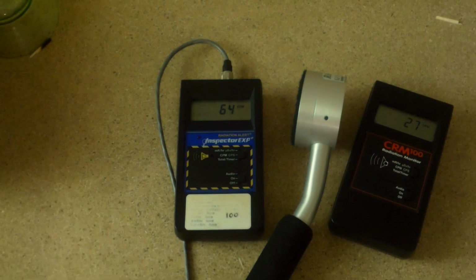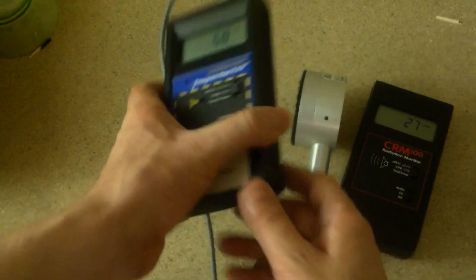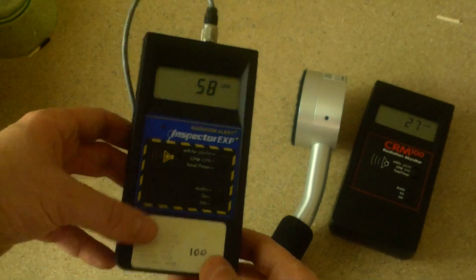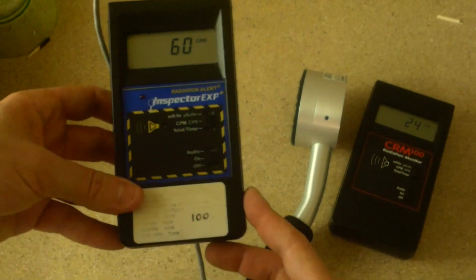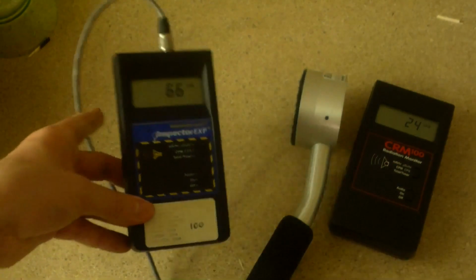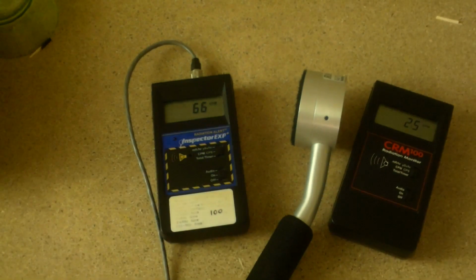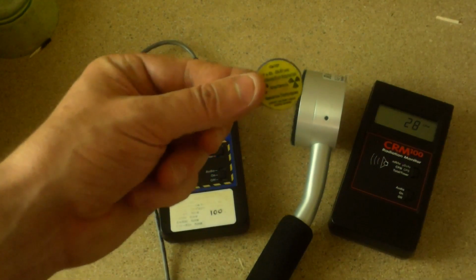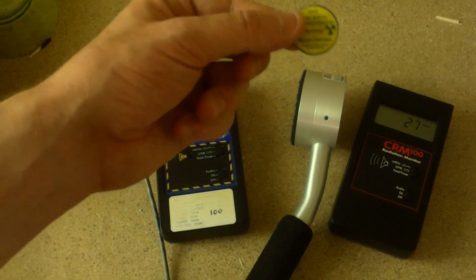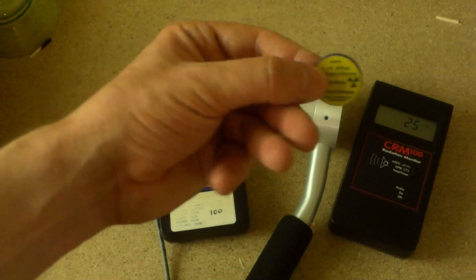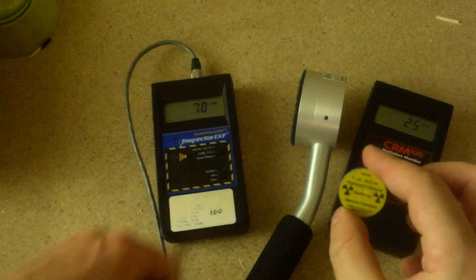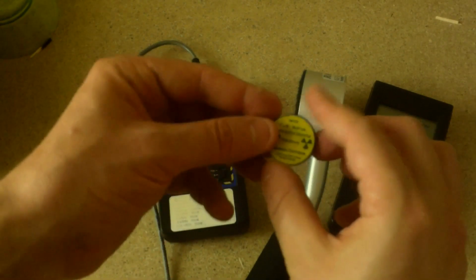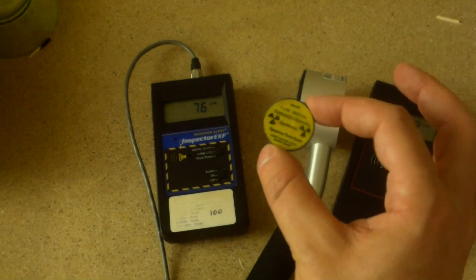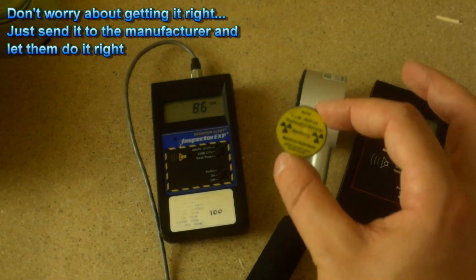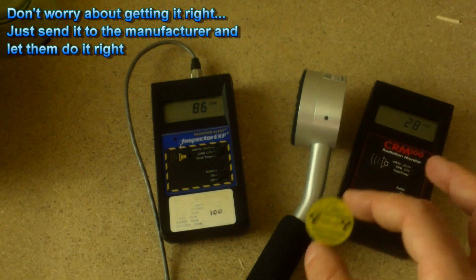Moving right along, calibration. Most of these units here need to be sent back to the manufacturer to calibrate. You can calibrate yourself if you have a powerful enough check source, but you can't just do it with a simple check source like the ones I have sitting around here. You need a cesium-137 check source of at least 370 kilobecquerels, that's 10 microcuries or more, and there are instructions in the actual packages that tell you how to do calibration. I don't do my own calibration. I don't even like to do it. So what I do is I send them off to the manufacturer to be calibrated.